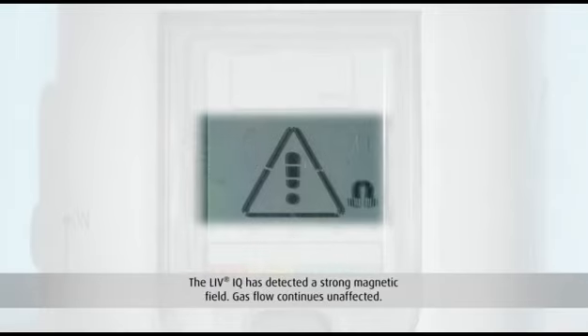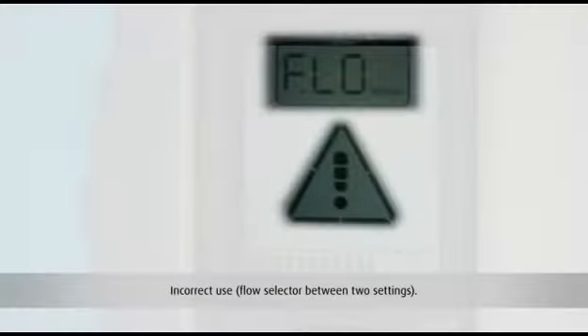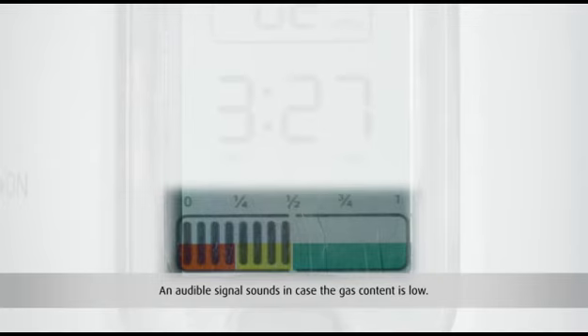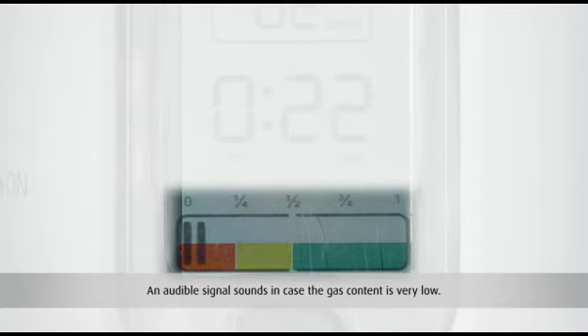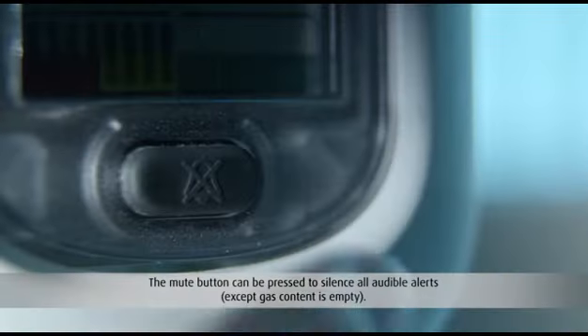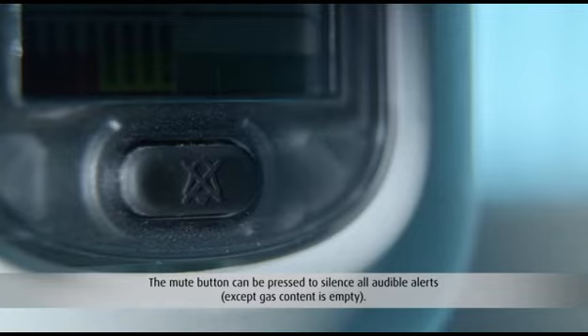The LIV IQ has detected a strong magnetic field. Gas flow continues unaffected. Incorrect use, flow selector between two settings. An audible signal sounds in case the gas content is low. An audible signal sounds in case the gas content is very low. An audible signal sounds in case the gas content is empty. The mute button can be pressed to silence all audible alerts, except gas content is empty.